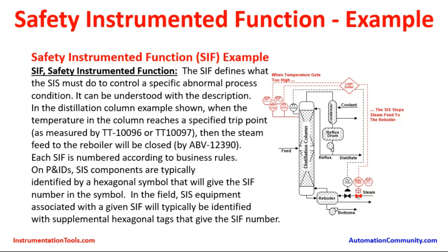The tag number of the instrument plus the SIF number of the particular system will be easily identified for the ease of the operation and maintenance team. This is very important for proper identification. Otherwise there could be a chance of error — instead of attending to TT10096, people may go and attend TT10046, which is also identical and in the same location. If the tagging philosophy is not properly maintained, there could be a chance of error by attending to the wrong instrument. So the tagging philosophy and SIF identification must be maintained in the field for error-free maintenance.